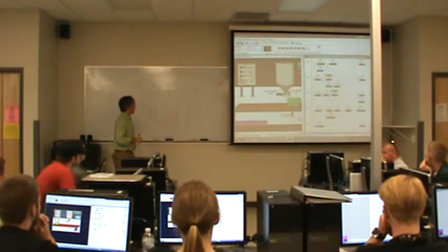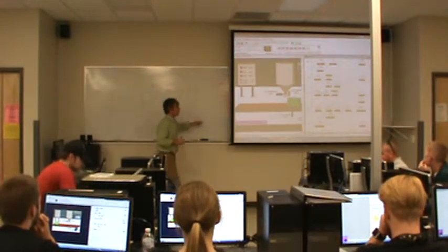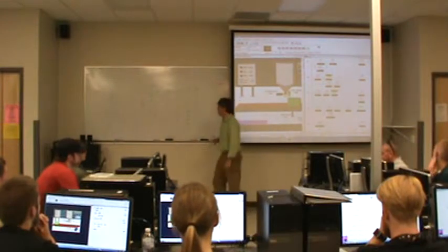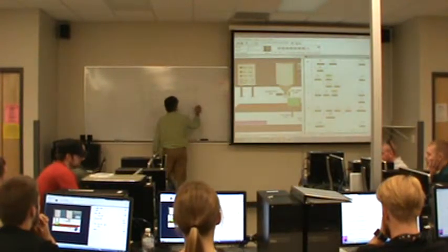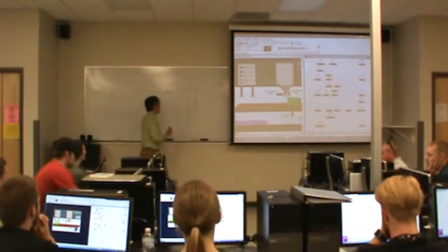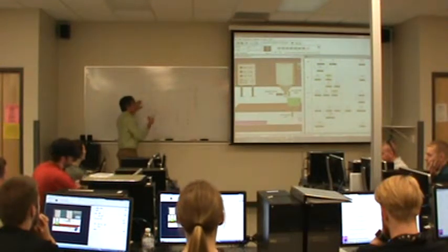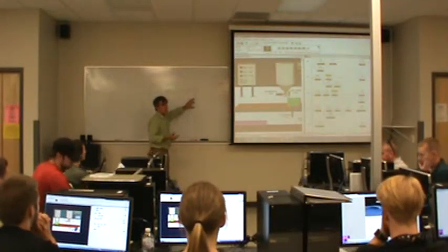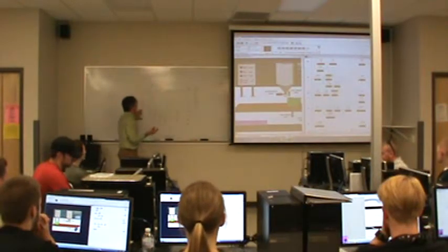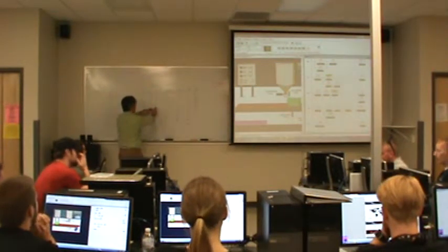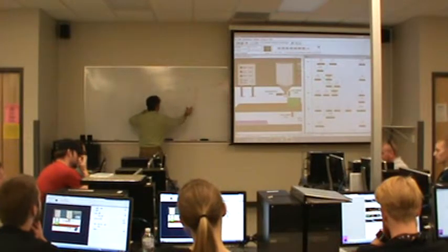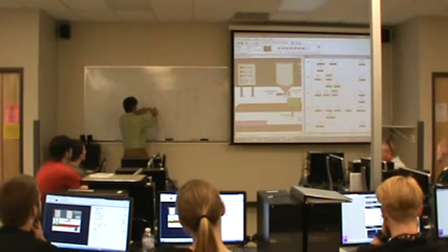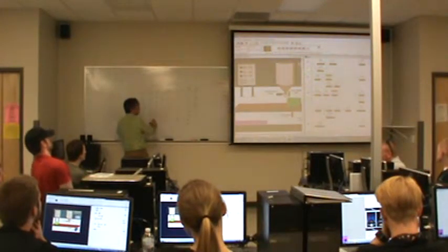Now notice that the full lamp right now is essentially programmed to follow the full bit, but we've got a single one here and a single one here that does not follow the full bit. Is it really worth it, though, to program these ones? Probably not. The full bit really indicates when the box is full. This set of conditions is just going to happen for one scan, because if prox is true and level is true, then very quickly the bit's going to be set and we're going to be down here.